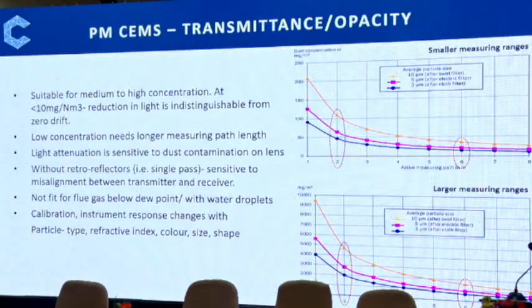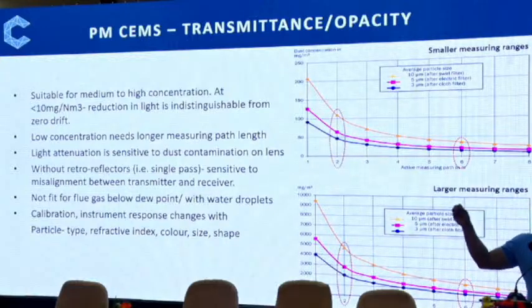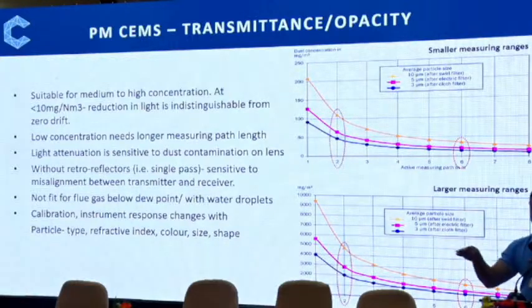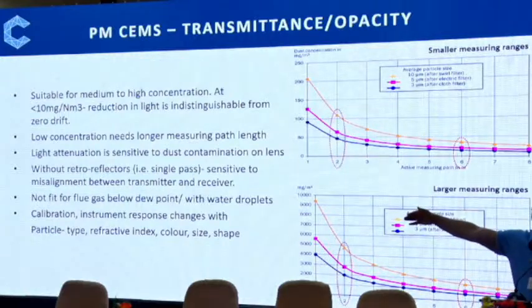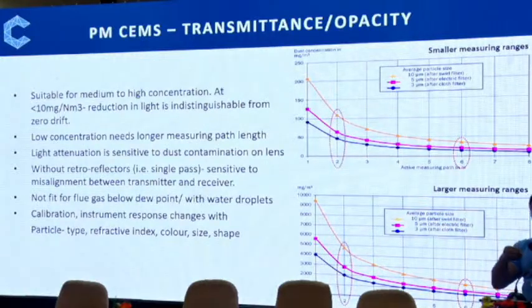Low concentration needs a longer measuring path length. So that's what I said. You know the ranges of the technology, but in some cases, if the diameter of the stack is big, you can monitor a little lower range. But beyond the limit, it will not be able to figure out how much light has been extincted if the dust is very low. Ultimately, the fundamental is that light has to reflect, go back and be lost. If the light loss is pretty low, you will not be able to figure out the difference. So it's better to choose the right technology.